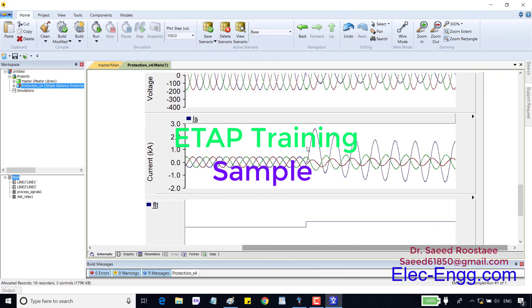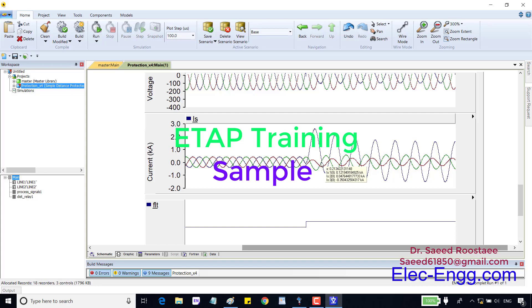Here is three phase current without fault, and AG fault happening at this time. As you can see, in the first half cycle fault current is maximum and the peak is also in this period. This period is called sub-transient time.